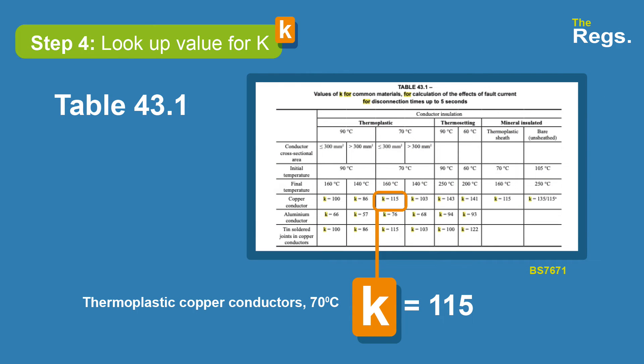Now we look up our value for K. This is table 43.1 in BS7671. We've got a thermoplastic cable, it's a copper conductor, it's 70 degrees C, and it's less than 300 millimetres squared. That gives us the column we want, and the factor for K is 115.